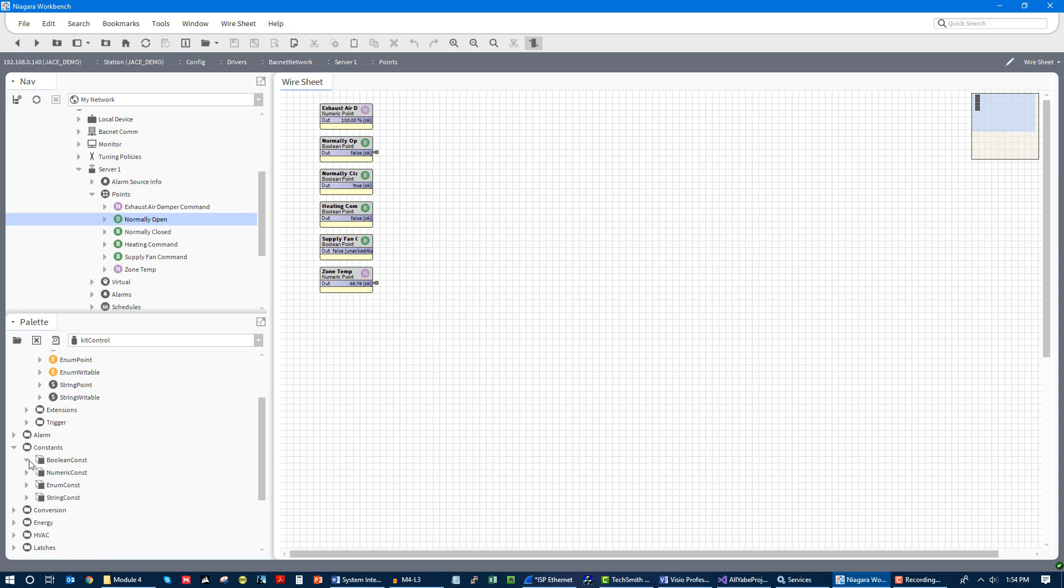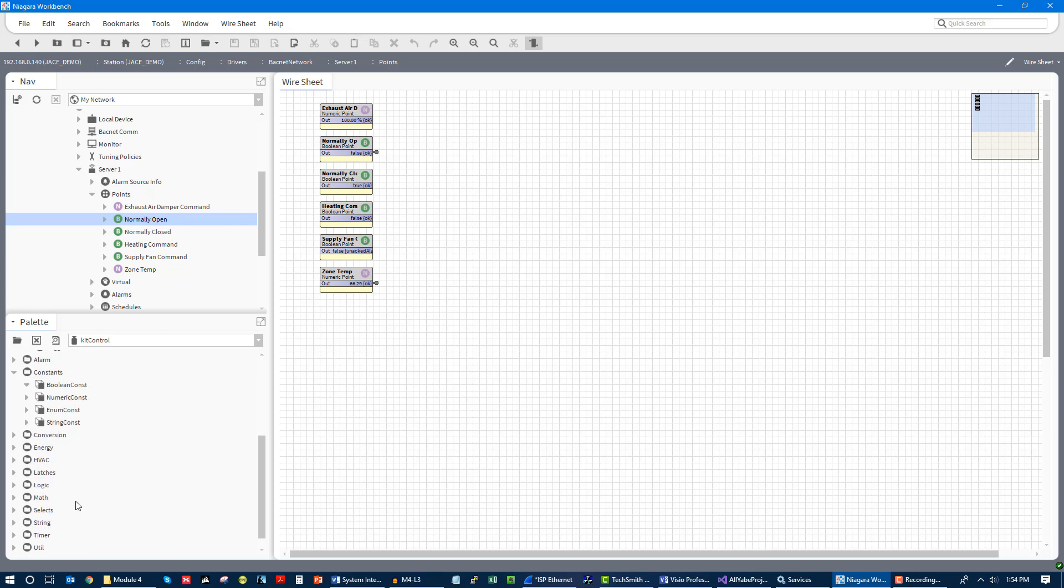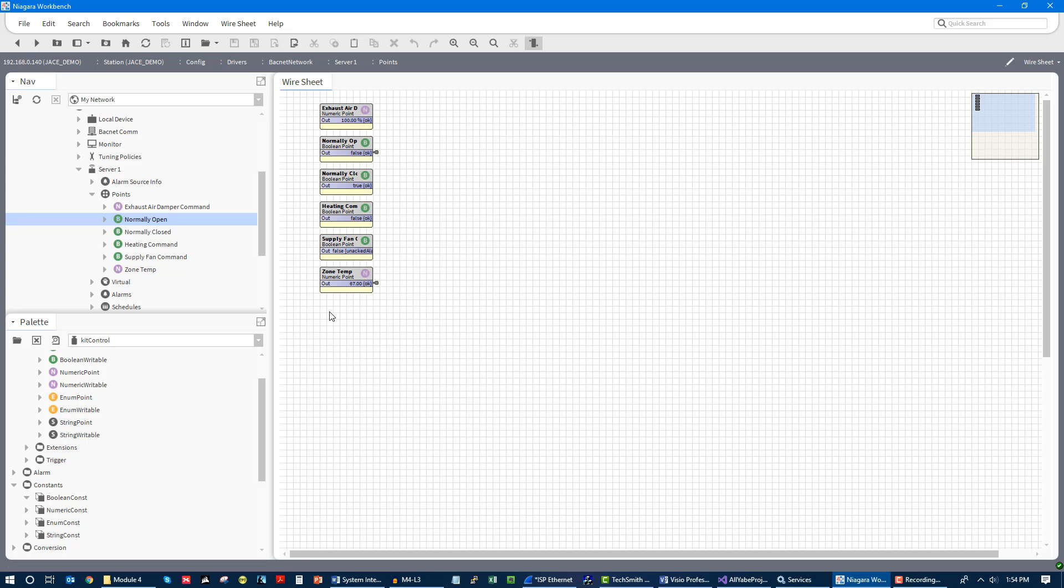In addition to these actual points, we also have what are called constants. Constants are essentially the same thing, but they are Boolean, numeric, enumerated, or string. But these are actual points that we put in there that are logical points. These constants are things that you would put in like set points you don't want people changing. Now I'm going to switch software to the actual software that is running the physical controller. We're going to look at the physical inputs and remember how I told you resistive inputs are scaled based on a pre-scaled chart—it looks at the resistance and then creates an output based on that.